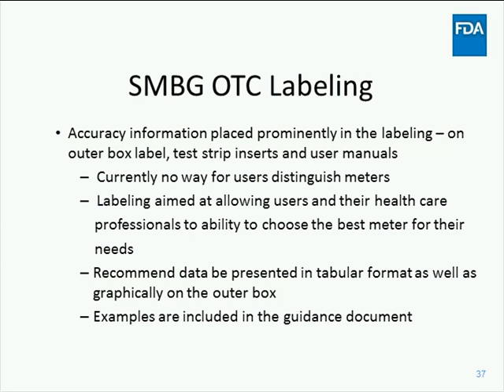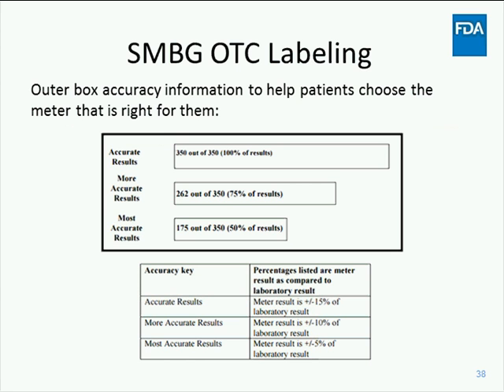Therefore, the SMBG guidance recommends that accuracy information be placed prominently on the outer box label and in the test strip package insert. The guidance recommends that the data be presented in easily understandable tabular as well as graphical formats. The tabular example that is provided in the guidance is similar to the accuracy tables currently used for these devices, with the percentage of meter results displayed within different accuracy bins, such as 5, 10, 15% of the comparator method. This is the example of the tabular format that's included in the guidance.